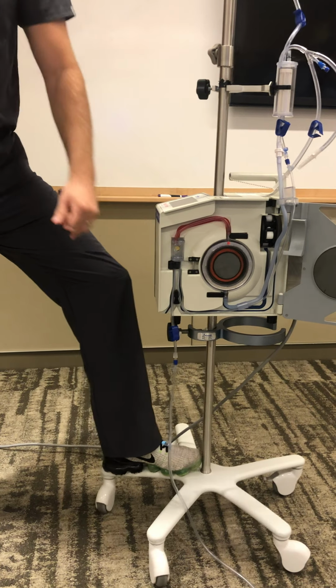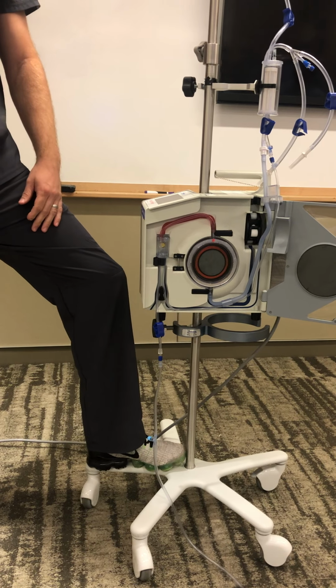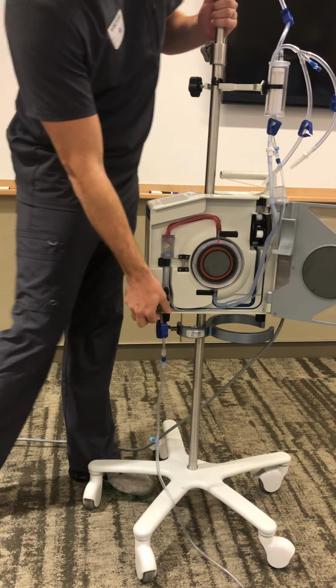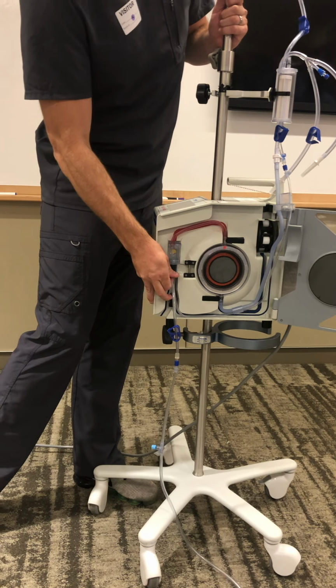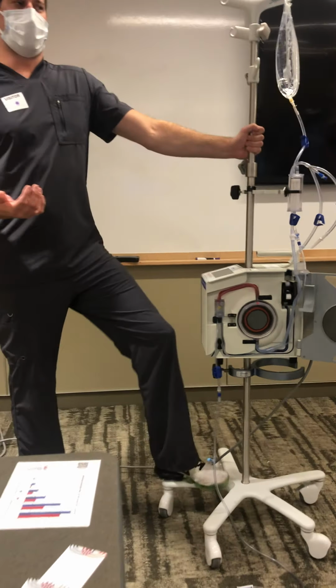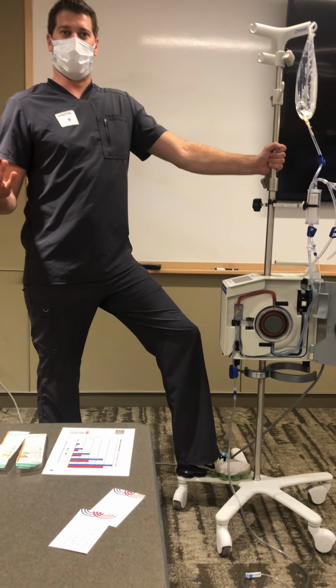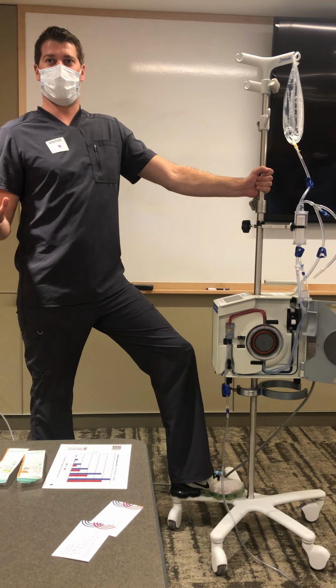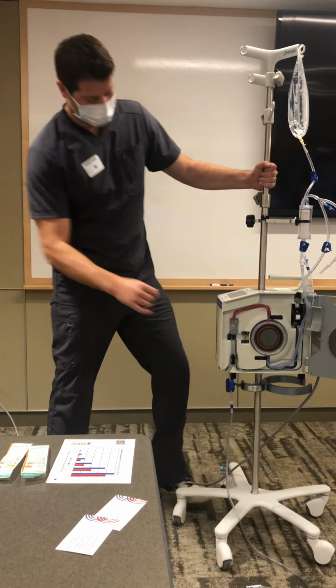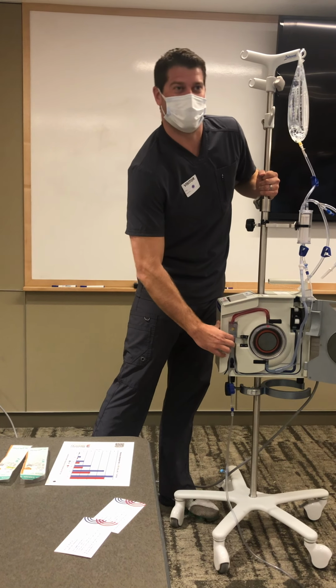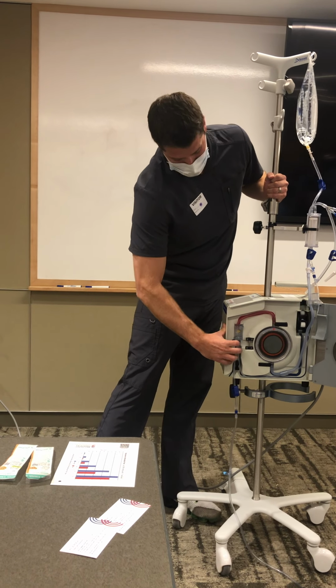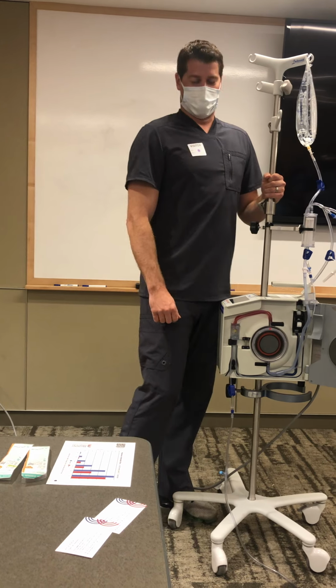This is an air sensor, it's ultrasonic, so it's looking through the tubing trying to sense air. So if you're in a hurry, and I completely understand why sometimes, it's only in halfway or 3/4 of the way, what's on the outside of the tubing? Air. So it could potentially give you an air message or an alarm that's really not real. Takeaway is this: take a hot second just to tuck that tubing in all the way.